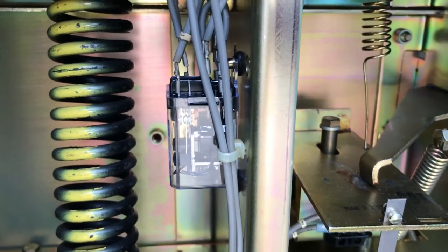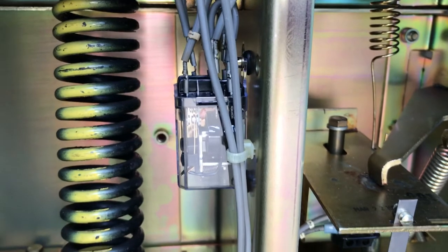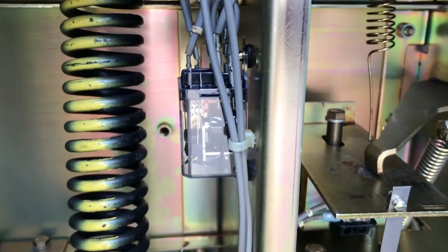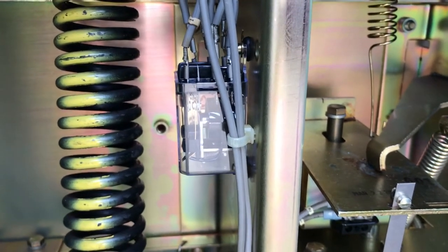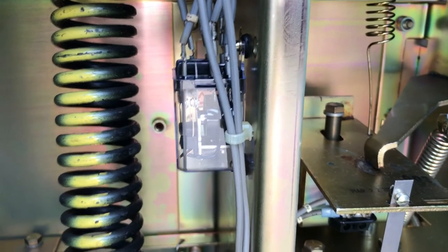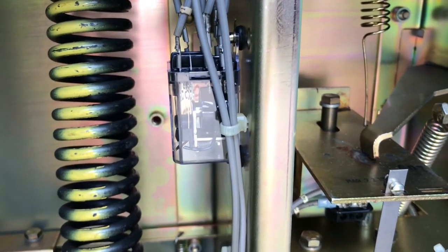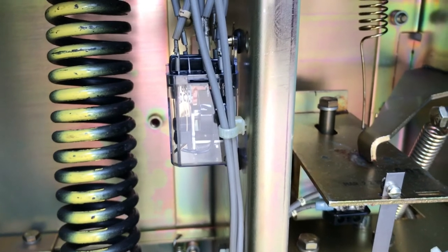I'm still holding the switch, so the anti-pump is still energized. With that being energized, it opens the circuit to the closing coil so that it can't attempt to close again.